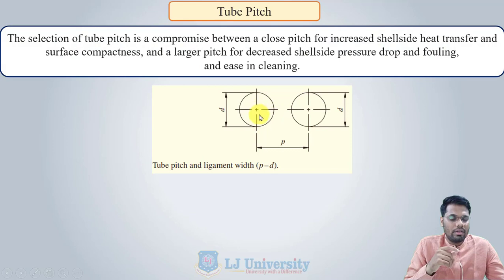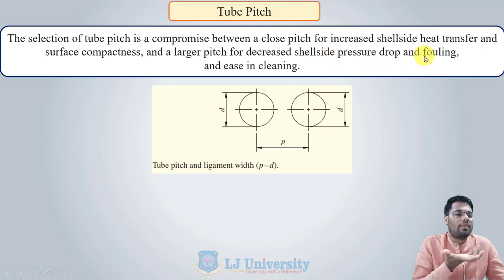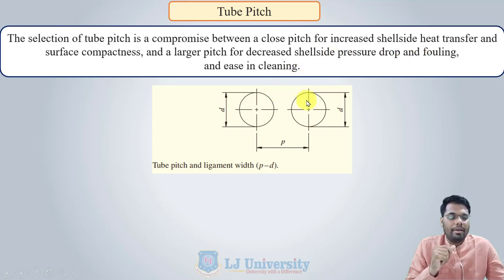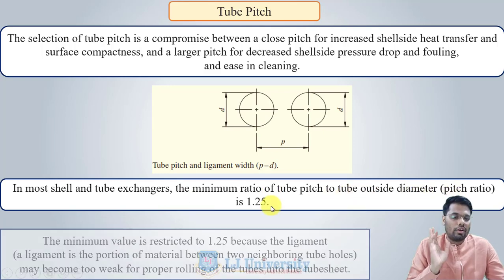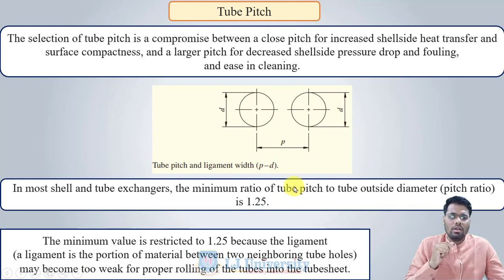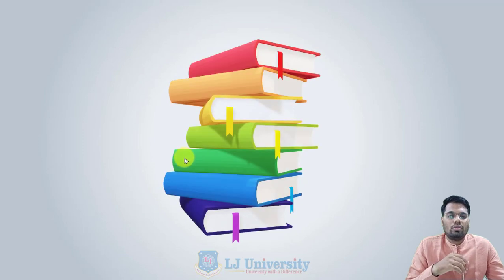Tube pitch is the center-to-center distance between two adjacent tubes. Selection of tube pitch is a compromise: a close pitch increases shell side heat transfer and surface compactness, while a larger pitch decreases shell side pressure drop and fouling and eases cleaning. In most shell and tube heat exchangers, the minimum ratio of tube pitch to tube outside diameter is 1.25, because the ligament — the portion of material between two neighboring tube holes — may become too weak for proper rolling of the tube into the tube sheet if the pitch is smaller.